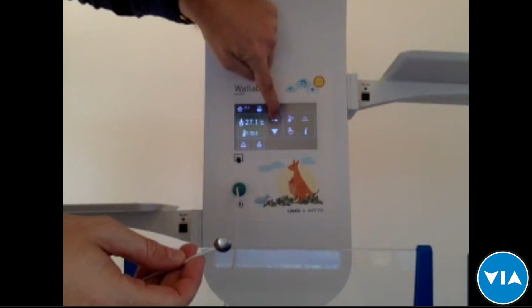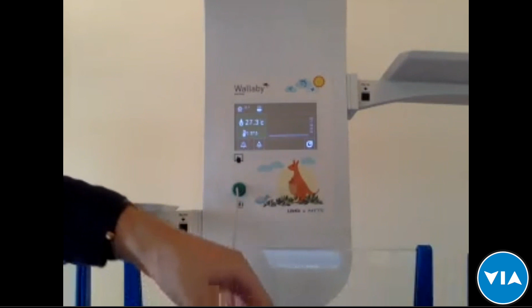The alarm doesn't go off now because we are still within 10 minutes from the warm-up time, so there are no alarms at the moment. At the moment, because we have a much higher set point than the actual temperature, it should alarm, but the first 10 minutes are alarm free.